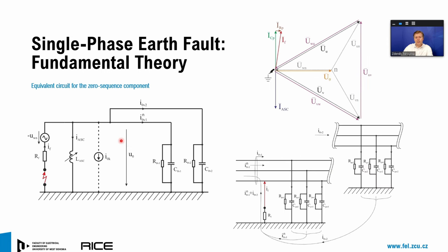Just the equivalent circuit under the earth fault, the single phase equivalent circuit for the zero sequence component. We have two feeders, the sound feeder and the faulty feeder. And here you see the state-of-the-art solution which we are using in the resonant compensated grid. This is the arc suppression coil connected in between the neutral point of the distribution transformer and the ground.